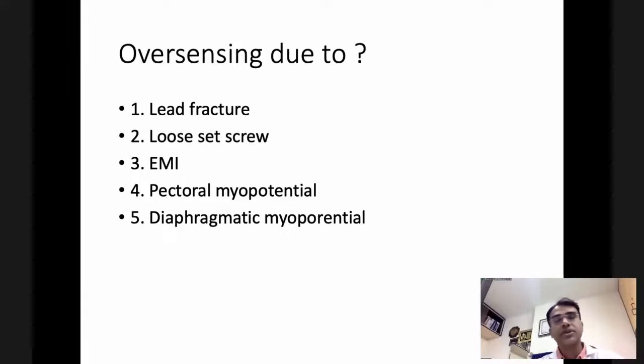Generally, nowadays we have near field sensing. That means the sensing of the ICD is from the tip to ring. So if EMI is from the external surface, it is often not reflected into the marker channel. So hence it generally does not lead to oversensing and shock. It can be reflected in the far field channel more than the near field channel.